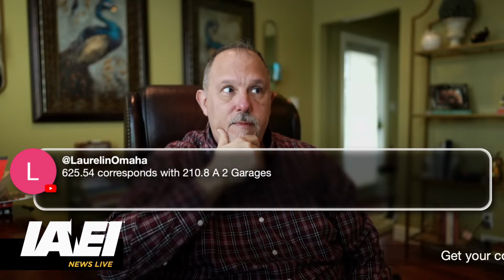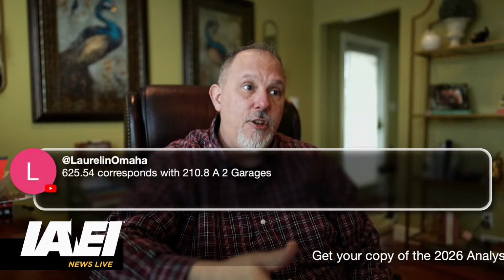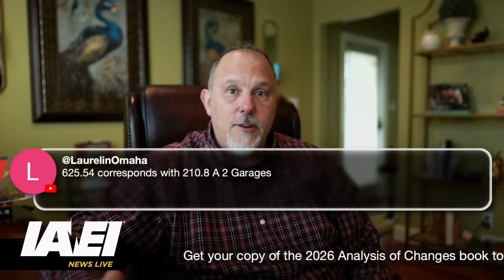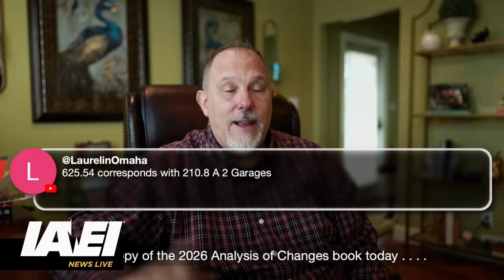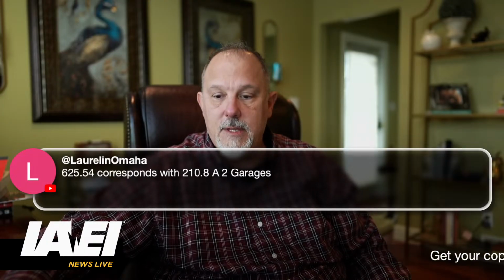Yes, it does correspond with 210.8A2. And Laurel, again, if it's hardwired and in the garage, then you don't need it. If it's hardwired outside, then you do, as long as it's on dwellings, outdoor outlets, other than those covered in 210.8A, exception number 1.